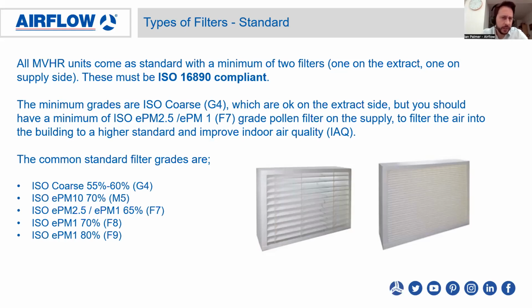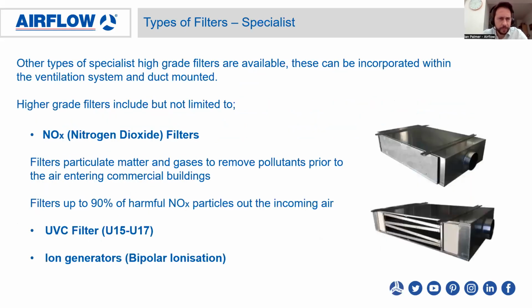Some of the common filter standards and grades that you'll come across are the ISO coarse, which is G4, ePM10, which is M5, ePM2.5 and ePM1 F7, ePM1 70%, which would be an F8, and ePM1 80%, which would be an F9 filter. These are some of the most common filters on domestic heat recovery systems. Other types of filters that you may also come across and that are available include nitrogen dioxide filters, NOx filters. These filter particulate matter and gases, and they remove pollutants prior to the air entering into buildings. These filter up to 90% of harmful NOx particles out of the incoming air.